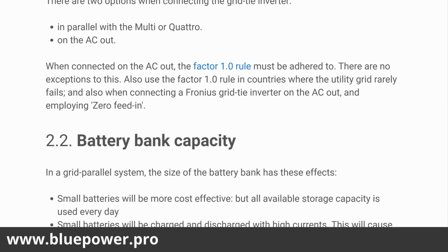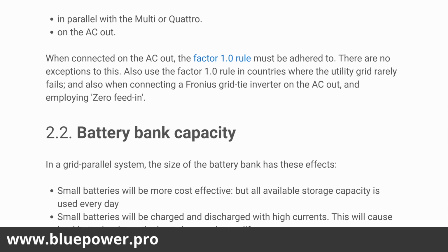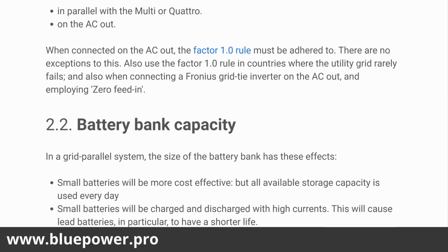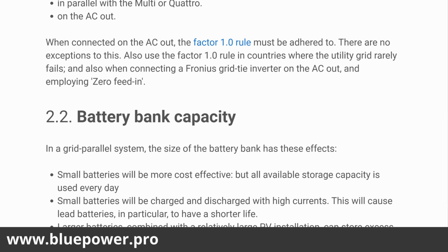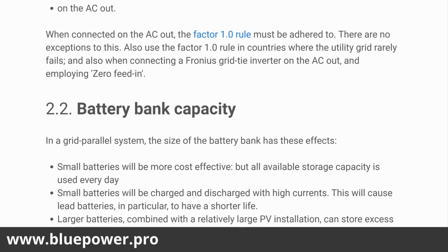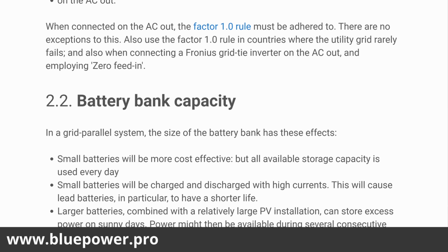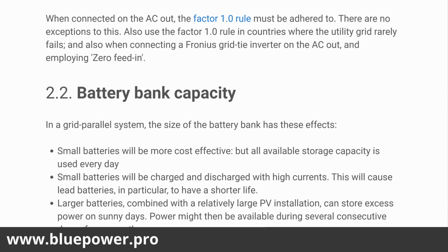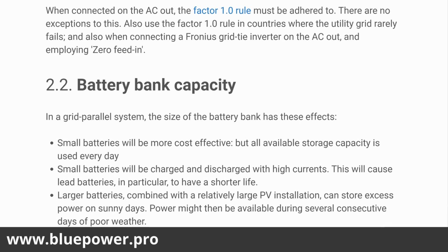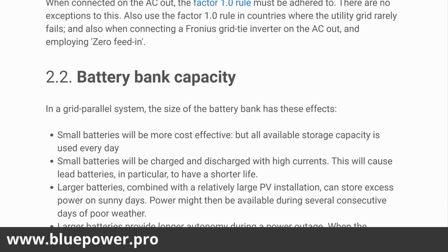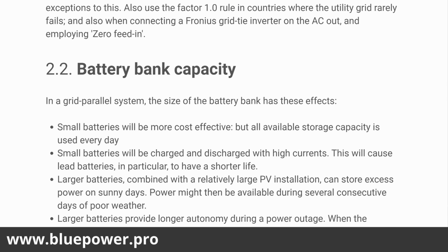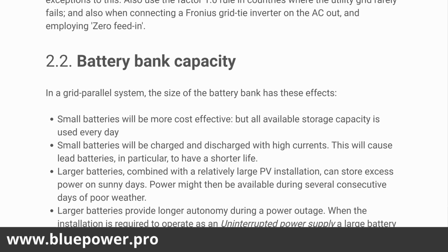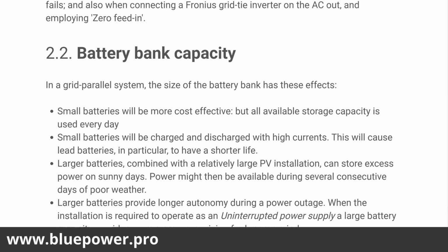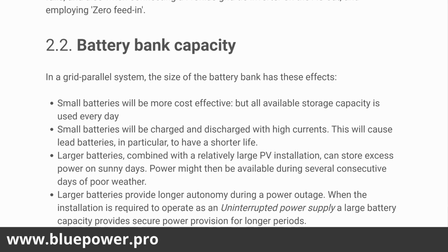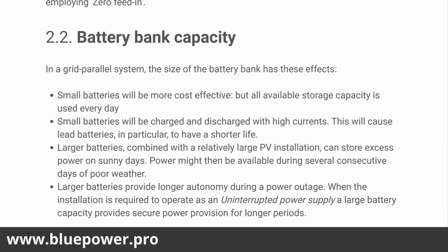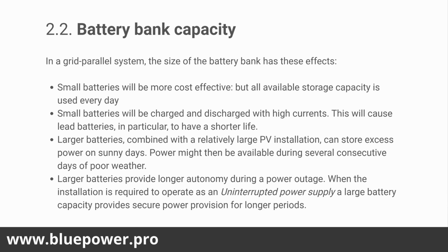The factor 1 rule just states that the PV inverter connected on the output of any battery inverter mustn't exceed the size of the battery inverter. So the maximum is the size of the battery inverter that it's connected to. So if it's on the output and you have a 30 kVA system, 3 10 kVAs in parallel, then you're going to have a limit of 30 kVA on the output of the system on the 3-phase grid line. Same for a 5 kVA inverter, can't exceed 5 kVA PV on the output. That is for cases where the PV inverter charges the battery and the loads are very low, you stand a chance to overload the inverter if you exceed 5 kVA. And the inverter's output can only feed or backfeed the maximum capacity of the inverter itself.